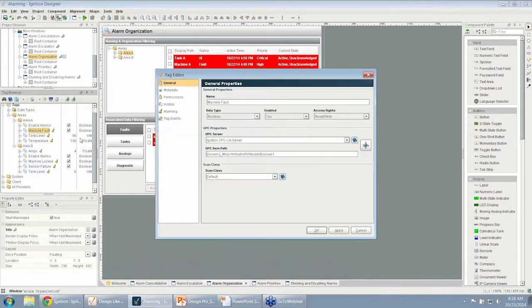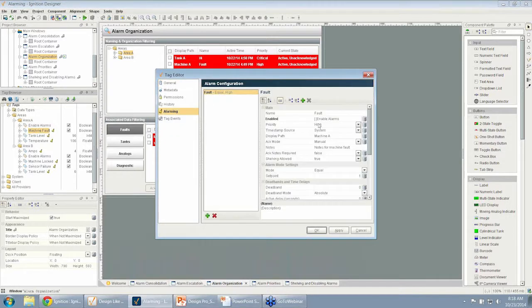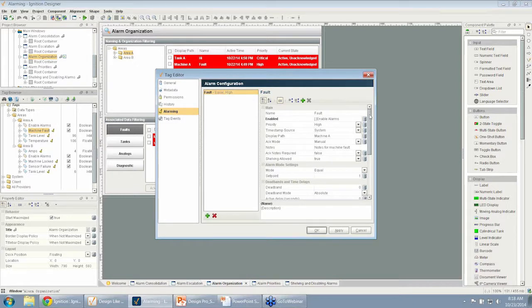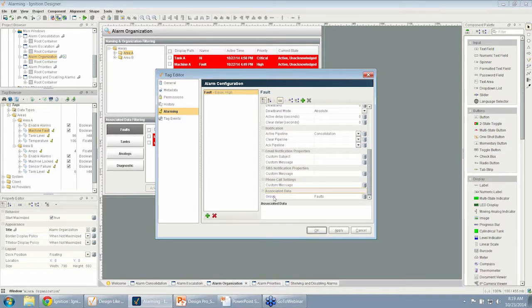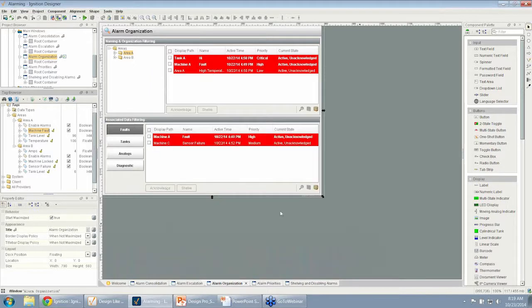If I go to alarming here, this screen plus icon allows you to add associated data to an alarm, and I can add anything I want. If I scroll down, you'll see there's an area for associated data, and they all show up as blue values. I have one called group, and the value of it is faults. I can just type whatever I want arbitrarily here, and I can add more than one of these groups if I want to.